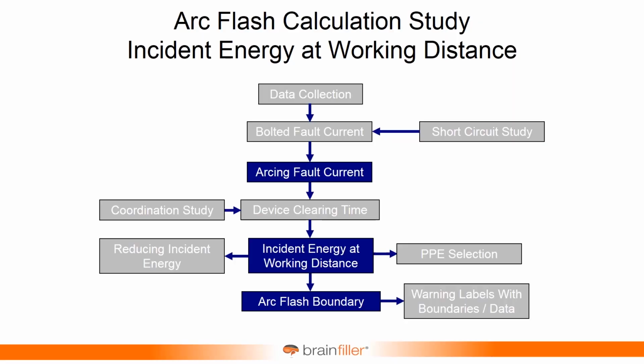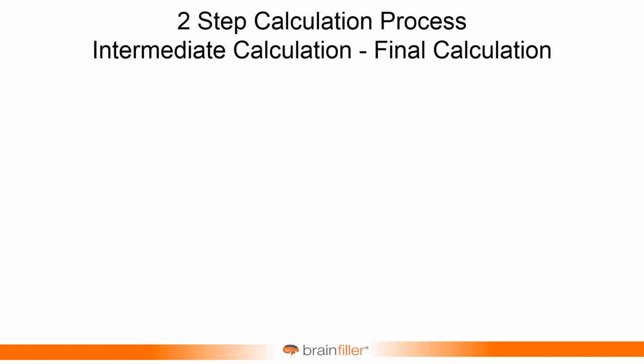Now the calculation process is going to be a little more complex. This is a flowchart from the book that I wrote years ago about how to perform arc flash studies. And in that process, I have a lot of the details grayed out, but the arc fault calculation, the arcing short circuit calculation, and the incident energy and the arc flash boundary, those are the three key numbers that you were calculating with the 2002 edition of IEEE 1584. Well, we still need these values, but how we go about this is completely different. As I mentioned, there's a calculation of the intermediate values, and then you fine-tune it based on your specific voltage.